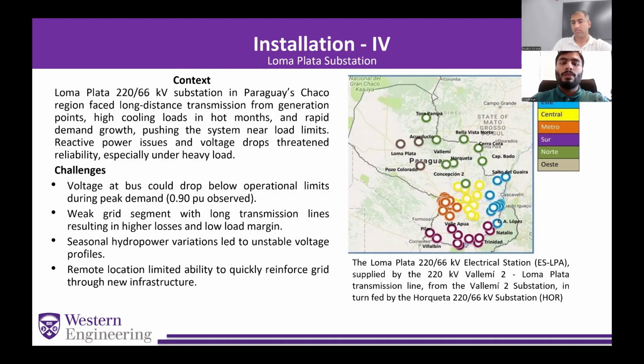Yeah. So our fourth case study is an installation in Paraguay in the Loma Plata substation. It has the same issue, that the voltage could drop below 0.9 per unit in hot months. And there was one more issue, that seasonal hydropower variation led to unstable voltage profiles. So they installed an SVC over there. Can you go to the next slide, please?